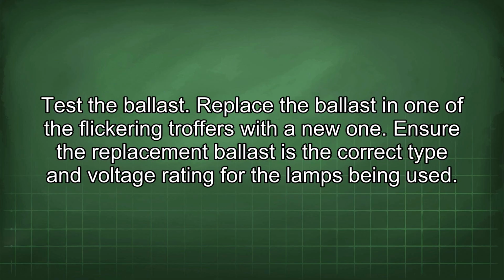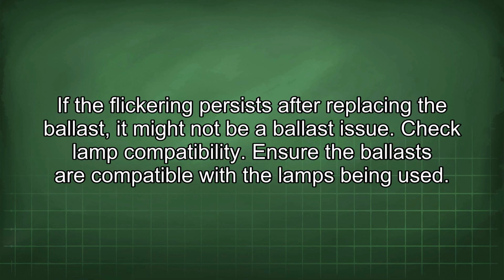Test the ballast. Replace the ballast in one of the flickering Troffers with a new one. Ensure the replacement ballast is the correct type and voltage rating for the lamps being used. If the flickering persists after replacing the ballast, it might not be a ballast issue.